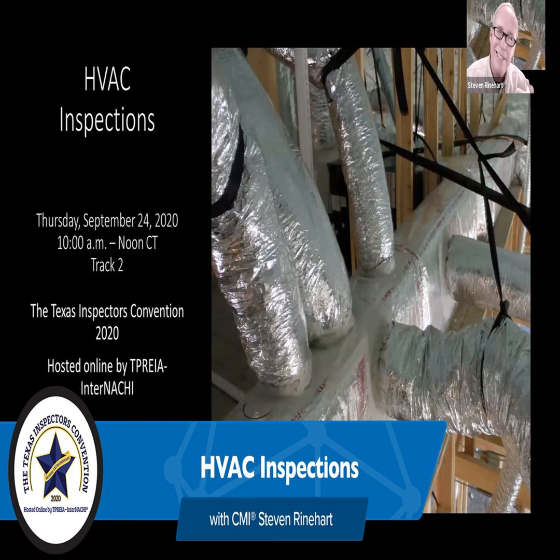Coming in the 80s, draft induced, forced air. Got a little fan, you notice, when you turn on the furnace, the first thing you hear is that fan go. It's going to evacuate any residual gases in that cavity and force air up the flue. And then you'll see the igniter go.